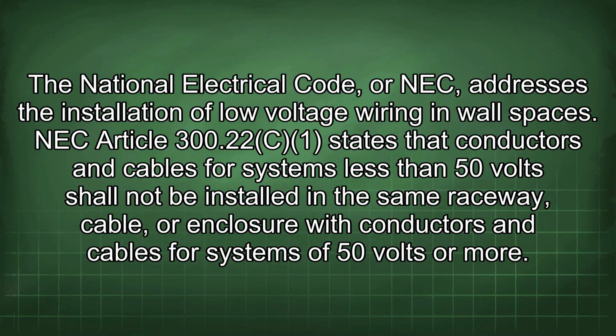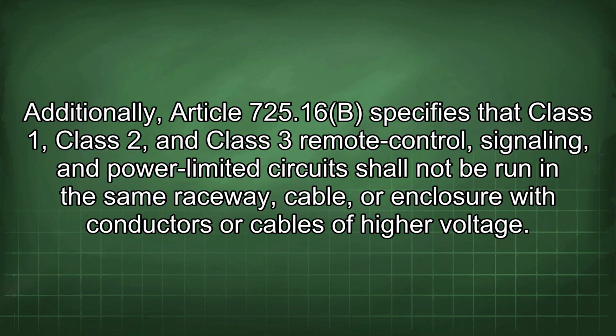The National Electrical Code, or NEC, addresses the installation of low-voltage wiring in wall spaces. NEC Article 300.22 states that conductors and cables for systems less than 50 volts shall not be installed in the same raceway, cable, or enclosure with conductors and cables for systems of 50 volts or more. Additionally, Article 725.16(B) specifies that Class 1, Class 2, and Class 3 remote control, signaling, and power-limited circuits shall not be run in the same raceway, cable, or enclosure with conductors or cables of higher voltage.